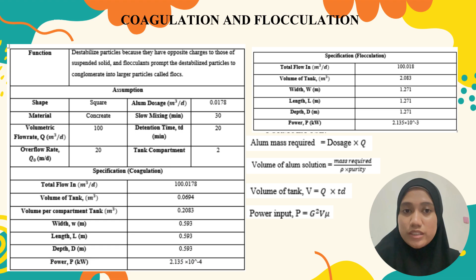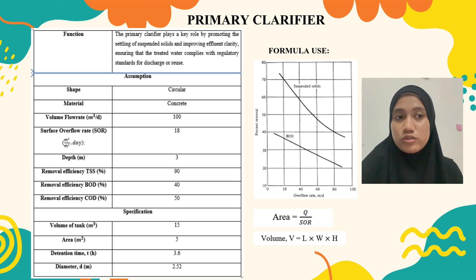Next, the primary clarifier. The primary clarifier removes suspended solids through gravity settling. So the sizing is based on the surface overflow rate, which represents the hydraulic loading applied to the clarifier surface. First, the required surface area is calculated by dividing the influent flow rate by the selected overflow rate. Once the area is known, the clarifier diameter can be determined assuming a circular tank. The side water depth is then selected according to standard design recommendations to complete the sizing. So this is the data sheet for the primary clarifier.